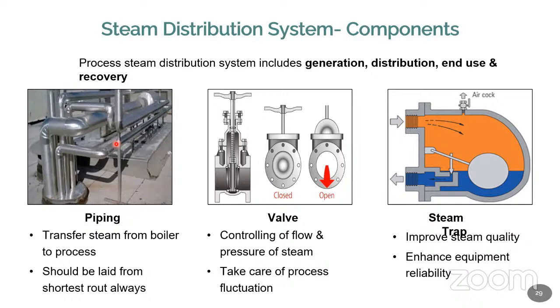Number one. Number two, if water droplets are available in the pipeline, they should be properly taken out. They should not go to the process because that will affect the process. So my requirement is only steam, not water or hot water. Okay. Sometimes this water will create rust in the system, rust in the equipment, rust in the process, or affect the quality of the system, especially for the food industries.